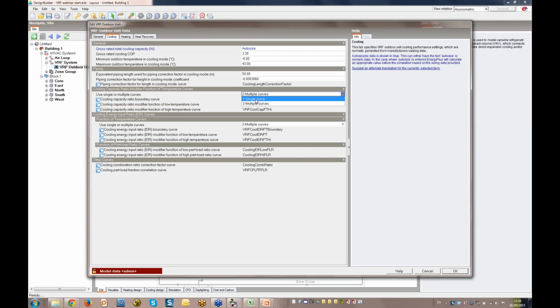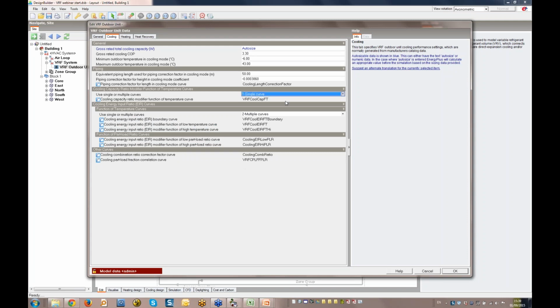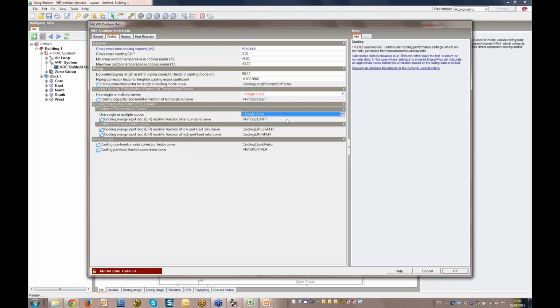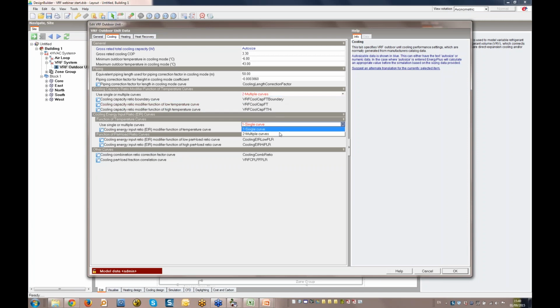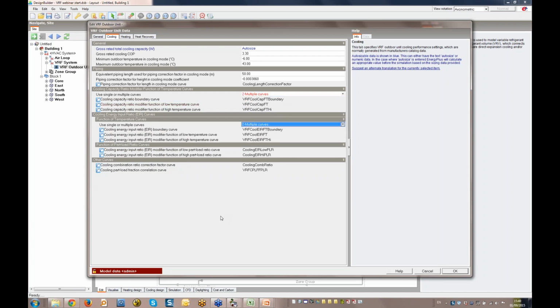It is possible to simplify VRF modelling where appropriate by selecting the single curve options. Jim will discuss when it might be suitable to use those single curve simplifications later. The generic curves provided are fine for the Energy Plus example system. However, when inputting data for a manufacturer system, you'll generally need to create your own curves.